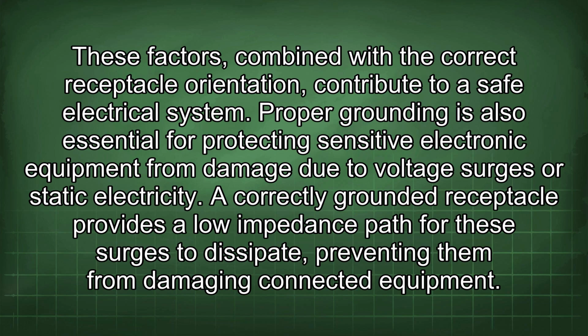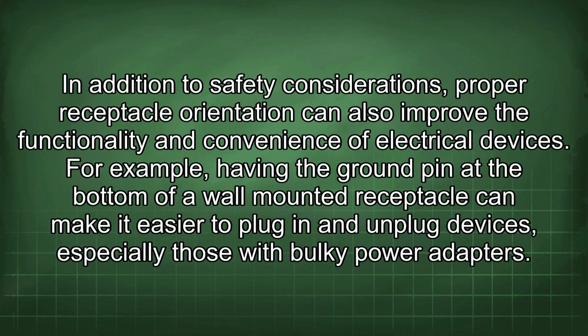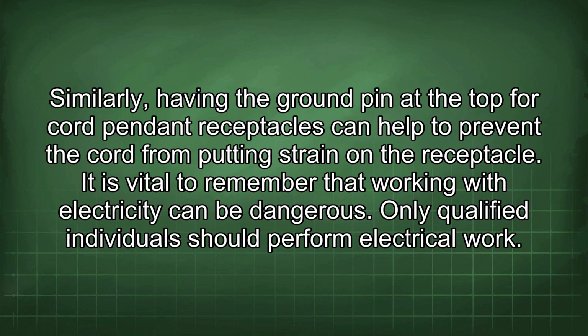Proper grounding is also essential for protecting sensitive electronic equipment from damage due to voltage surges or static electricity. A correctly grounded receptacle provides a low impedance path for these surges to dissipate, preventing them from damaging connected equipment. In addition to safety considerations, proper receptacle orientation can also improve the functionality and convenience of electrical devices. For example, having the ground pin at the bottom of a wall-mounted receptacle can make it easier to plug in and unplug devices, especially those with bulky power adapters. Similarly, having the ground pin at the top for cord pendant receptacles can help to prevent the cord from putting strain on the receptacle.